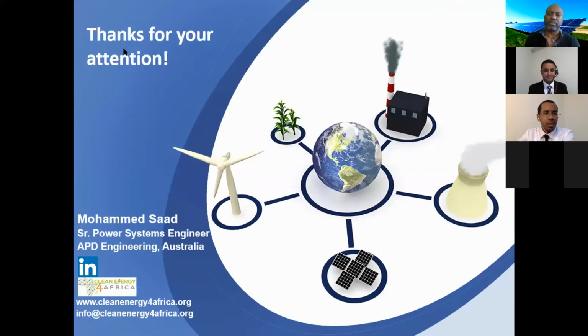There's one question from Abdulaziz: what is the difference between capacitor banks and synchronous condensers in operation? A capacitor bank is a static device, so it will not do much during dynamics. As far as I know, it will inject reactive power during steady state and do some power factor correction. But during a fault, we need dynamic response from a device that will dynamically respond and inject reactive current to the system to support voltage, which the capacitor bank won't be able to do.